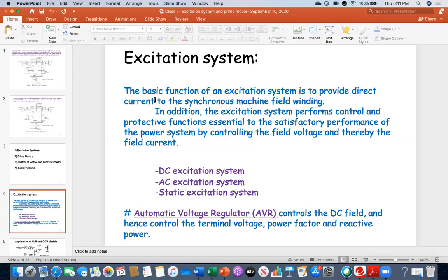The basic function of an excitation system is to provide direct current to the synchronous machine field winding. Whether it's salient pole or non-salient pole, there are physical magnetic poles, and you have to provide DC current to excite or magnetize that. That is the basic function. In addition, the excitation system performs control and protective functions which are essential for satisfactory performance of the power grid by controlling field voltage and hence the field current. Now the question is, how to excite the field?